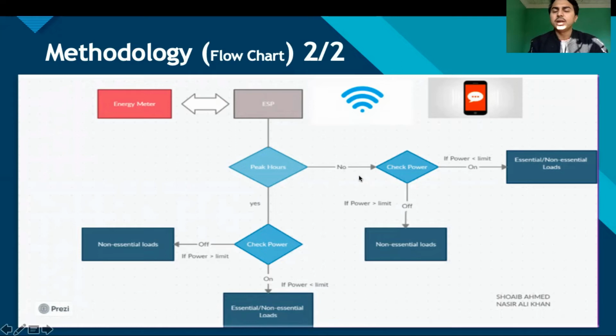If there are no peak hours, in off-peak hours, it again checks the power first. If the power is greater than the user-defined value, it turns off the non-essential loads; if less, it keeps both essential and non-essential loads on. This power limit changes depending on the period: during peak hours we have a lower power limit, and during off-peak hours we can have a greater power limit.